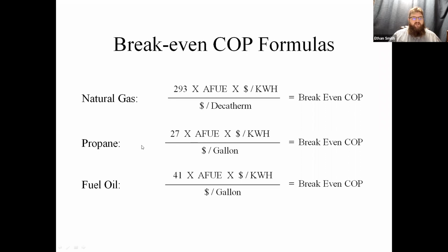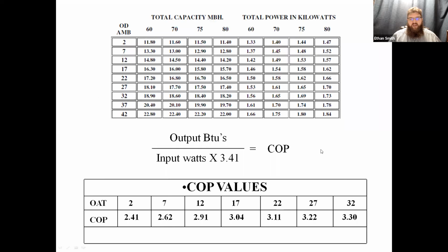Same thing with propane. We're going to divide all that by dollars per gallon. Fuel oil, dollars per gallon again. And that will give us a number that is our break-even COP. So what we have to do with that is take our break-even COP, and then go into our unit and plot some COPs. This is that same 16 SEER unit that we were working with before, and what I've done is gone in here and calculated my COPs using that formula.